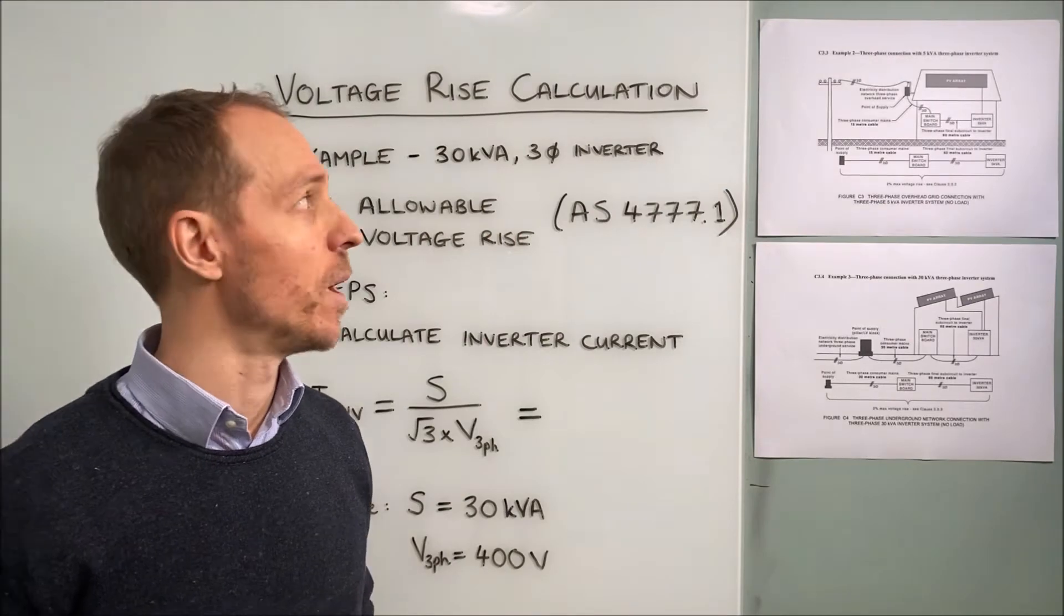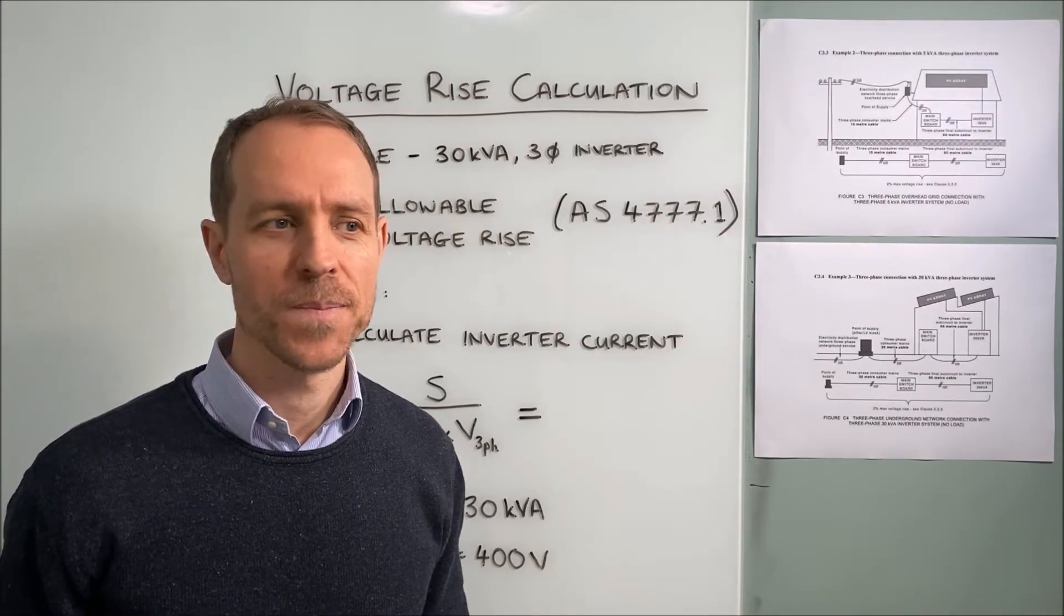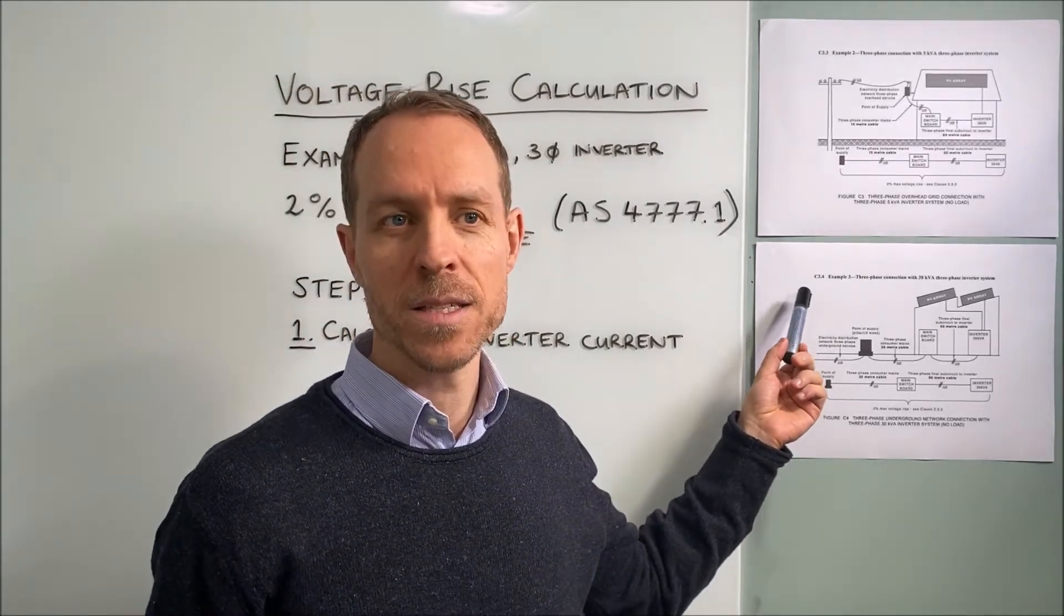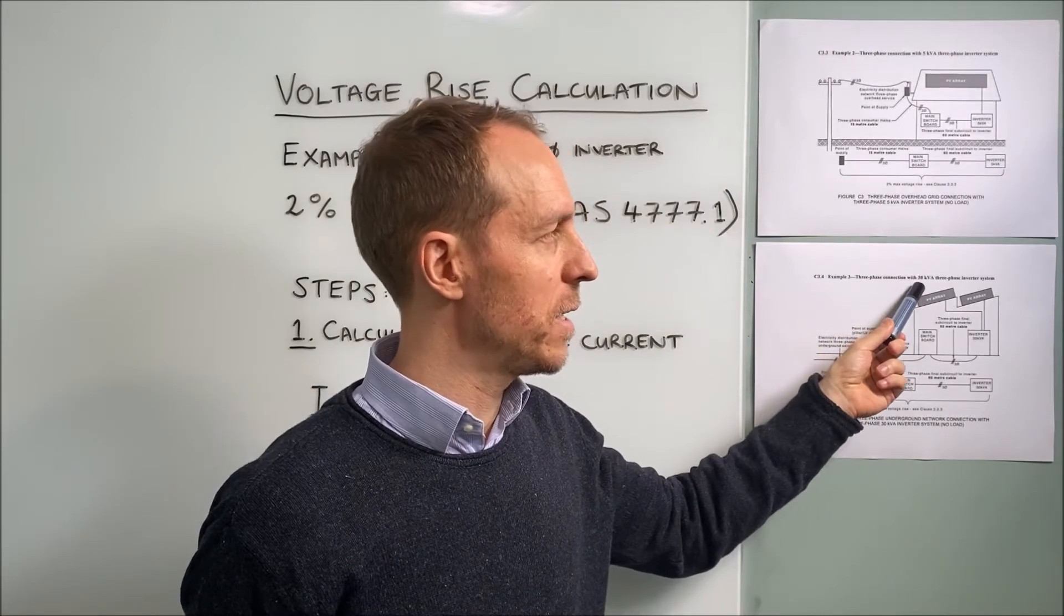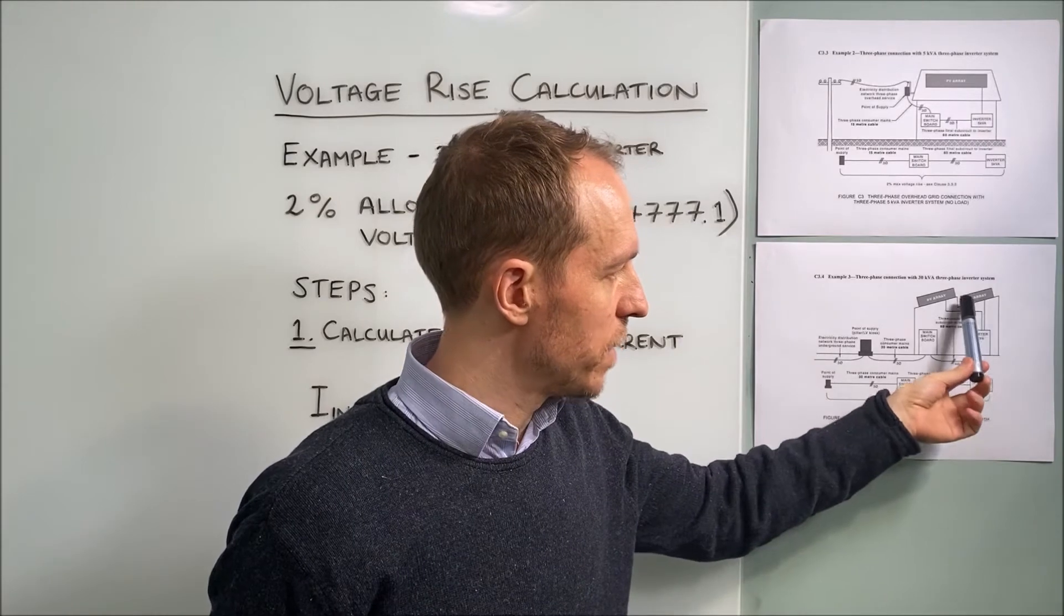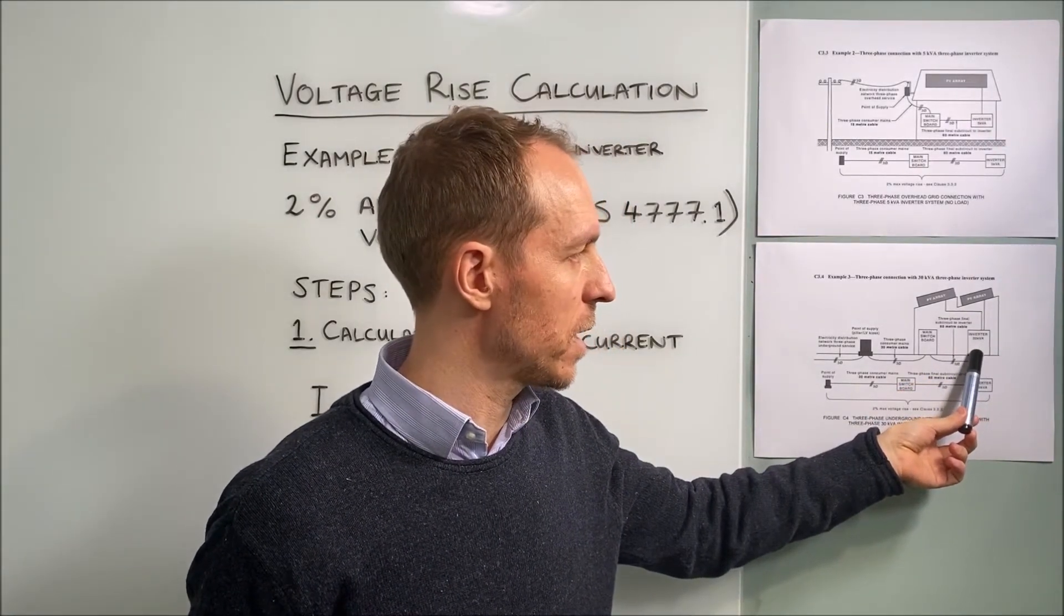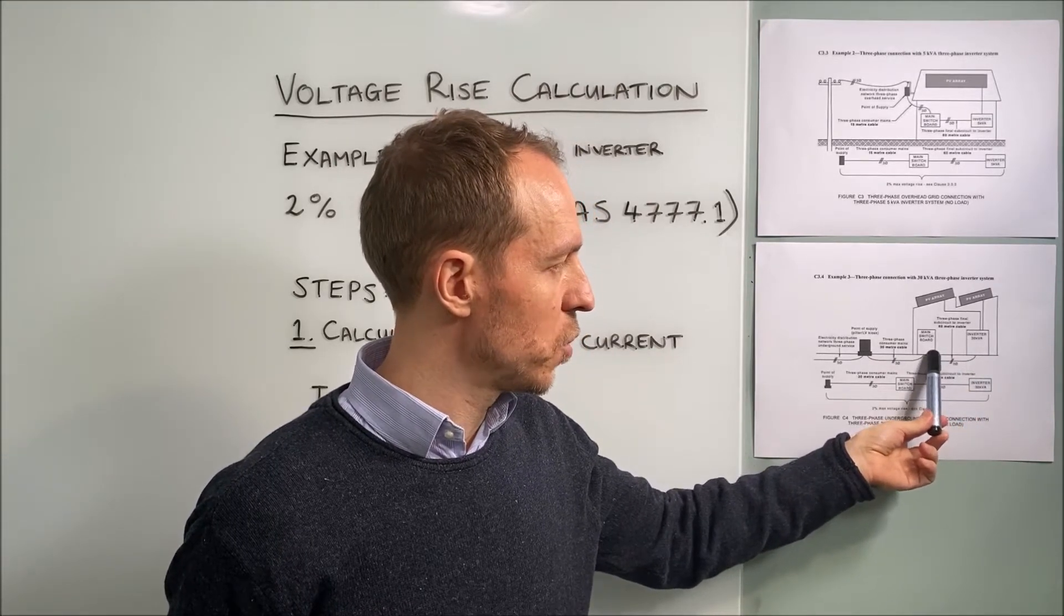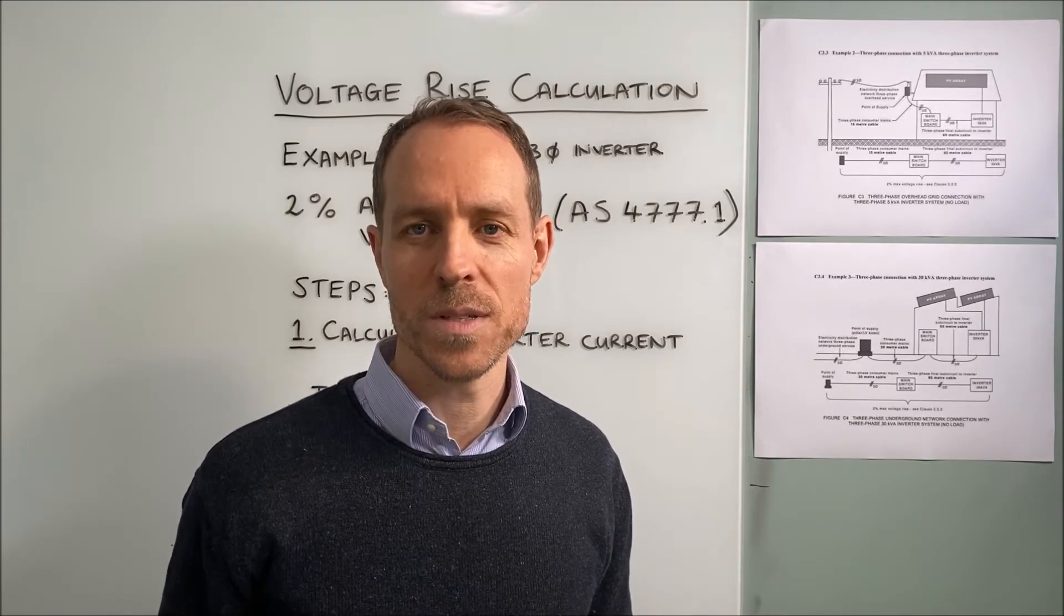Today I'm going to show you how to perform a voltage rise calculation by hand and using software. The example is going to be based on that taken from AS4777. This is a three-phase 30kVA inverter system. We have the two sets of PV arrays connected to the 30kVA inverter and two underground cable sections connected to the point of supply.